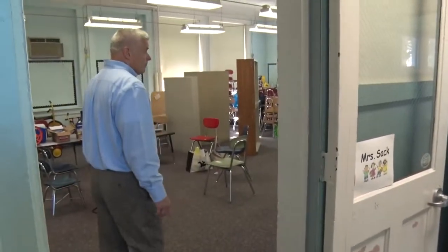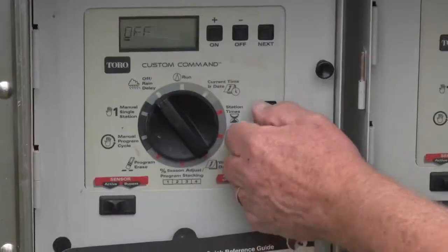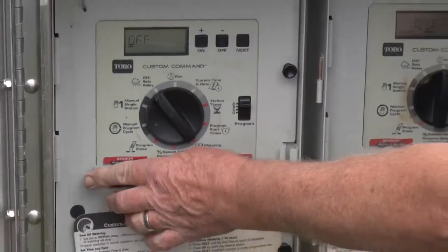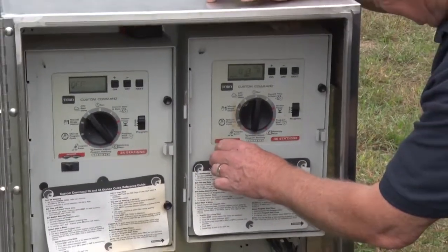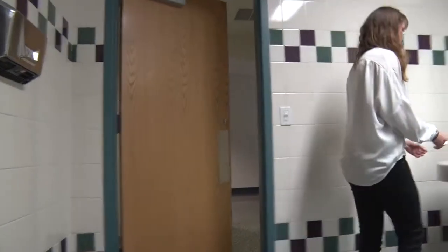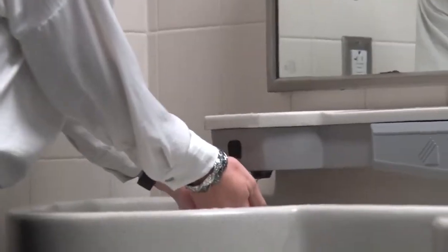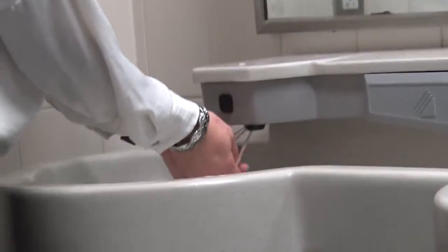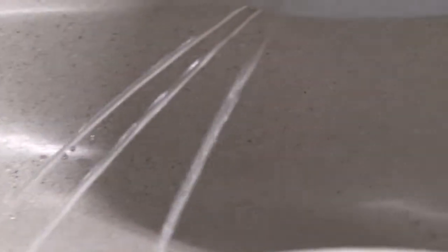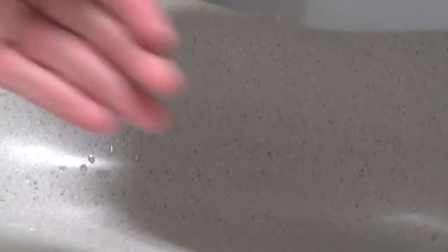A second walkthrough is conducted prior to sampling, during the stagnation period of 8 to 48 hours, to ensure that the water is not running anywhere in the school and that the school is vacant of staff and students. This includes toilets that may be running. Be sure to turn off any irrigation sprinkler systems. During this walkthrough, it is advisable to deactivate or turn off water outlets that are operated by motion sensors. Should these sinks be accidentally activated when sampling, it would compromise the stagnation time required and sampling would need to be postponed and rescheduled.